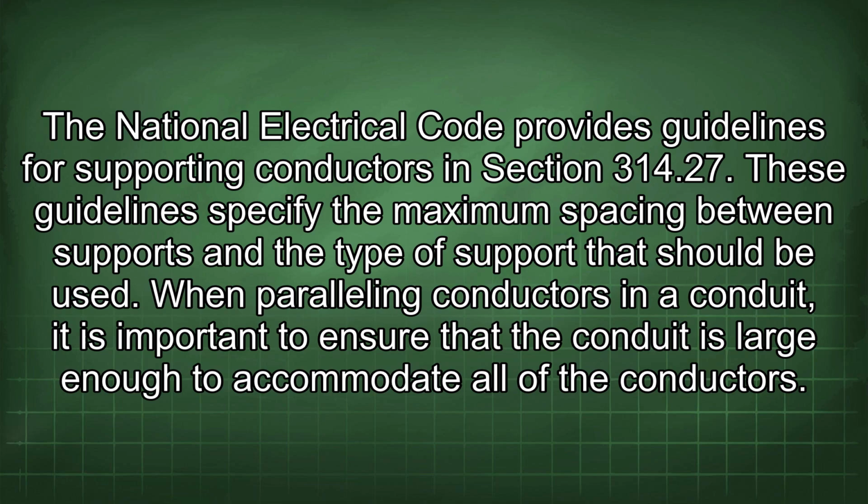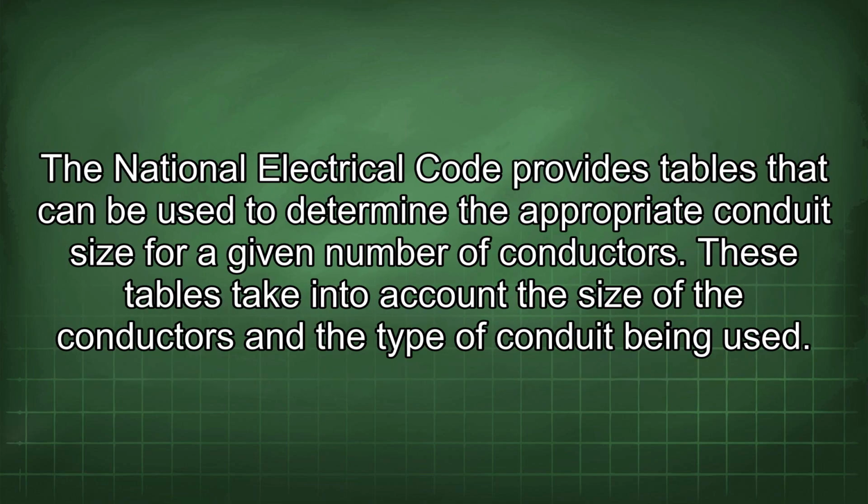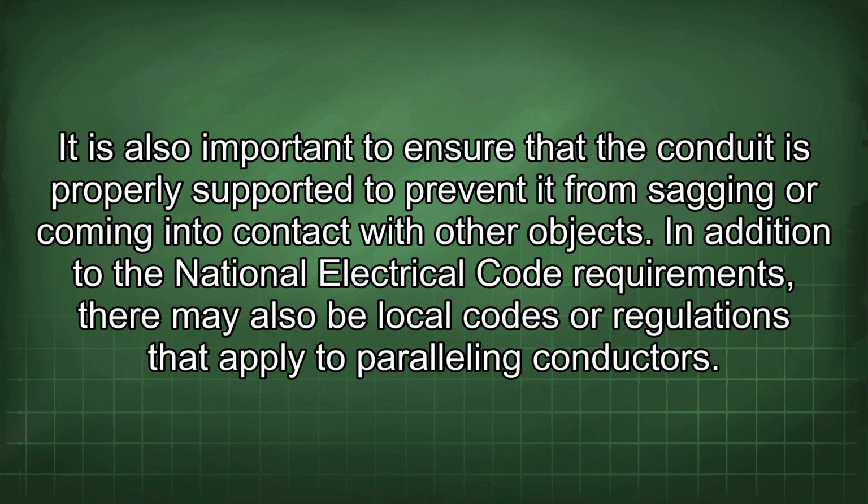When paralleling conductors in a conduit, it is important to ensure that the conduit is large enough to accommodate all of the conductors. The National Electrical Code provides tables that can be used to determine the appropriate conduit size for a given number of conductors. These tables take into account the size of the conductors and the type of conduit being used.